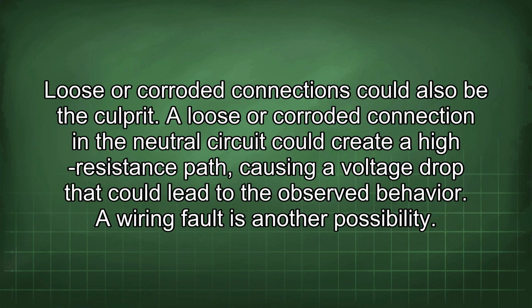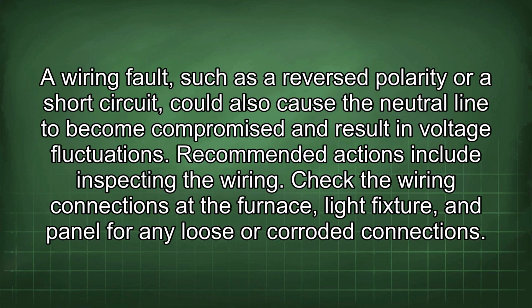Loose or corroded connections could also be the culprit. A loose or corroded connection in the neutral circuit could create a high resistance path, causing a voltage drop that could lead to the observed behavior. A wiring fault is another possibility. A wiring fault, such as a reversed polarity or a short circuit, could also cause the neutral line to become compromised and result in voltage fluctuations.